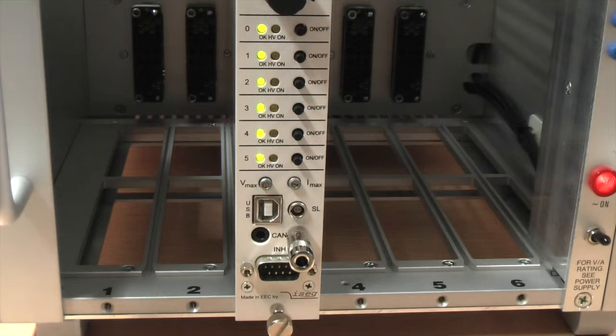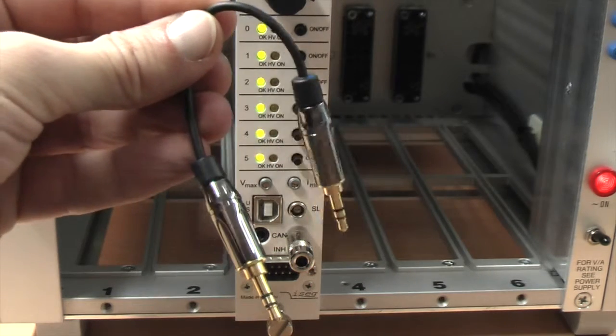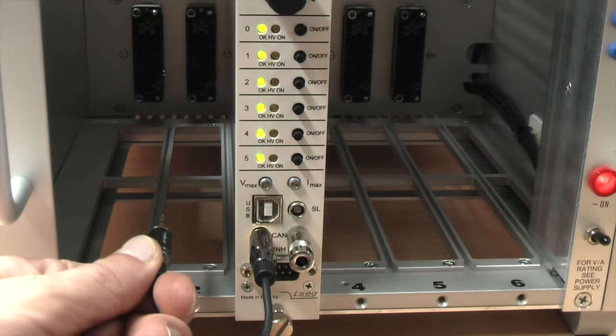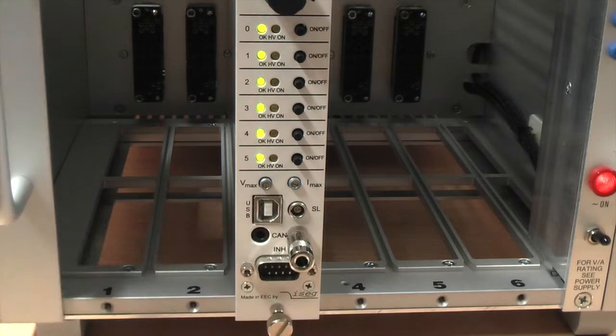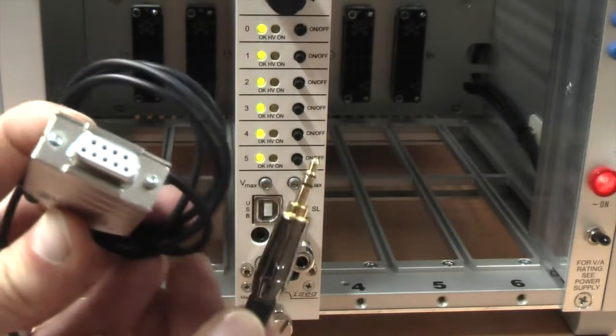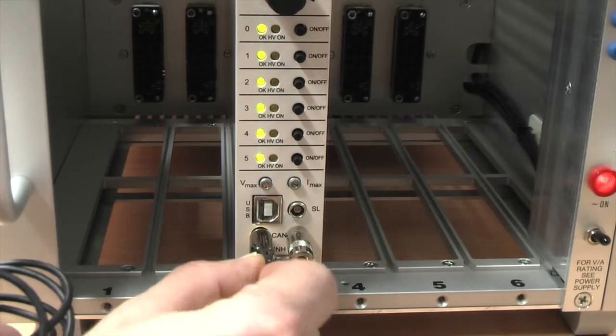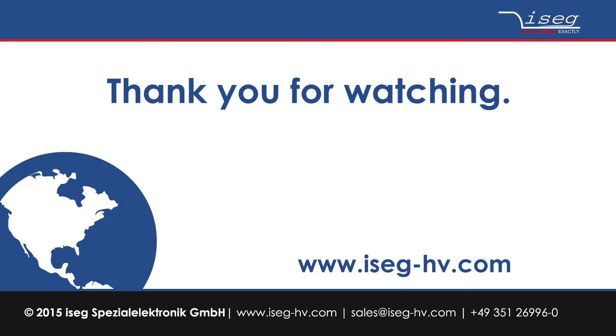If you want to connect two or more NHS units to the same CAN line, linking cables are available from iseg. You connect the linking cable to the free CAN connector and the other end to one of the connection points of the other module. To connect the modules via CAN bus to a computer you need a special adapter cable which is part of the shipment; this adapter is then connected to the CAN interface you are using. Control via USB interface or CAN interface will be explained in a different video. Many thanks for watching — should you have any questions feel free to contact us via our website www.iseg-hv.com.